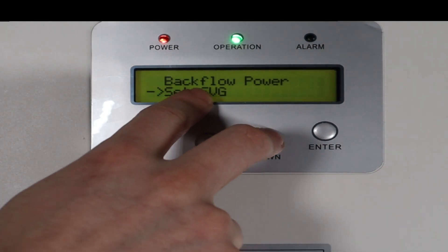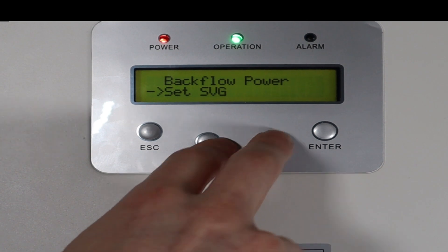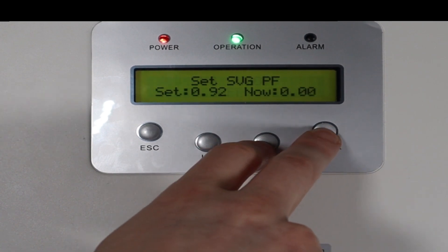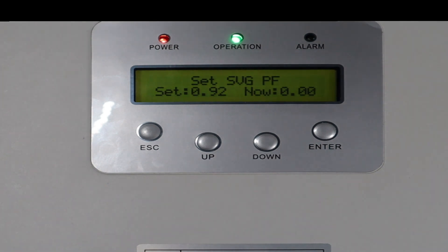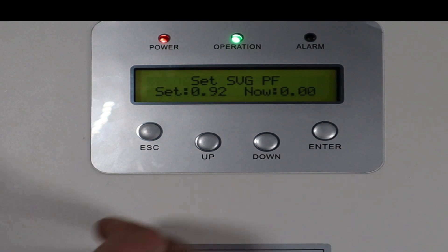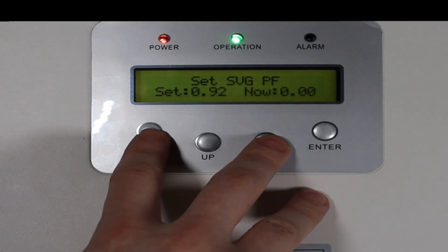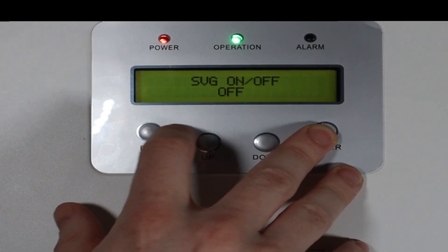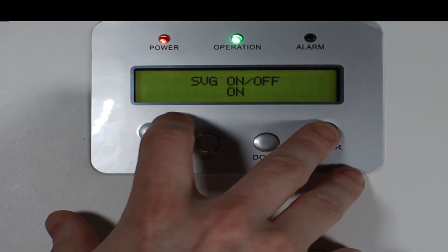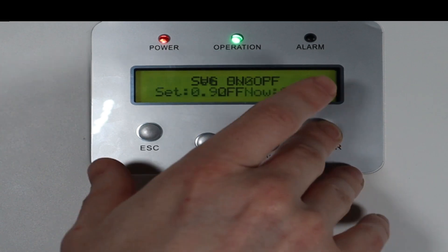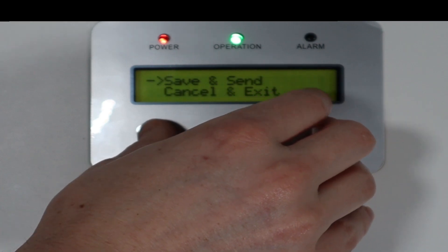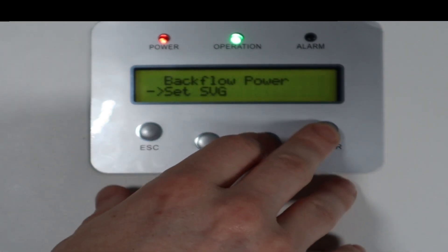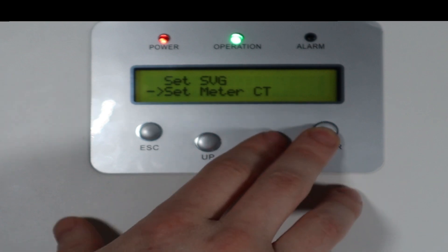Then SVG is a power factor correction function. Effectively, you can program this to correct the, well, change the power factor of the inverters. So that when the EPM sees a bad power factor, the inverters change their power factor, and it corrects that power factor. So it's very useful function. Okay, but you have to turn it on. You see, but I don't want it on for the time being. Only if you need it, and the customer has this requirement, set that up. So yeah, that's not something you would always set up by default.